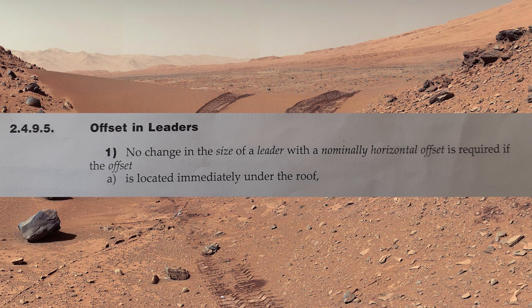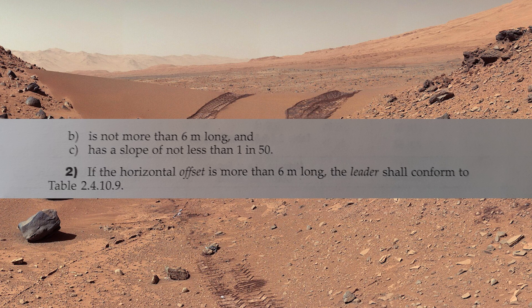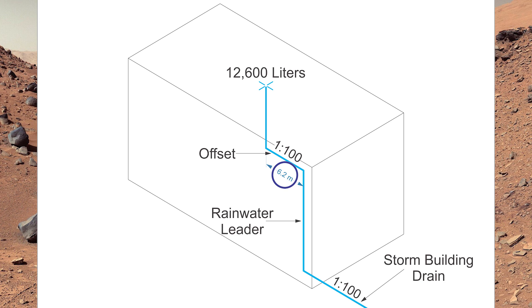Let's look at clause 2495: offsets in leaders. Number one — no change in the size of the leader with a horizontal offset is required if the offset is located immediately under the roof, is not more than six meters long, and has a slope of not less than 1 in 50. Number two — if the horizontal offset is more than six meters long, the leader shall conform to table 24109, which is the same table for sizing storm building drains. Our offset here is 6.2 meters — more than six meters long — and it is also sloping at 1 in 100.